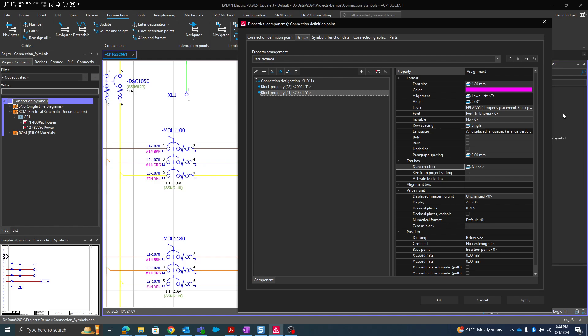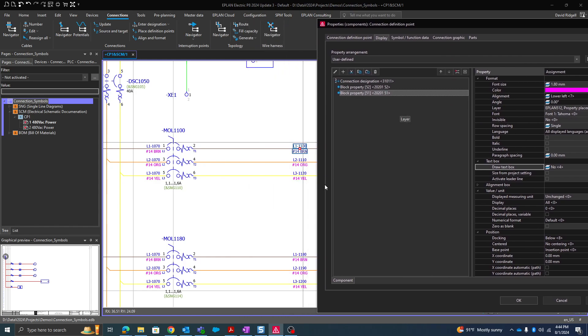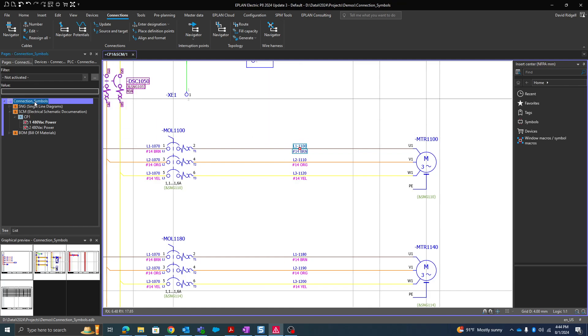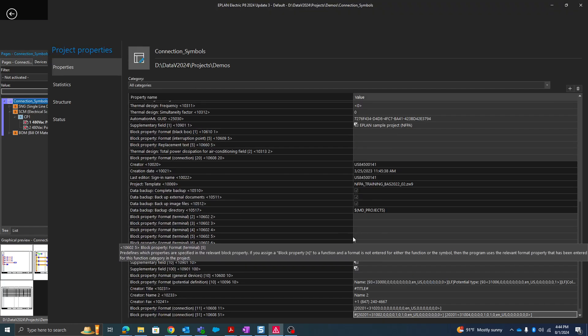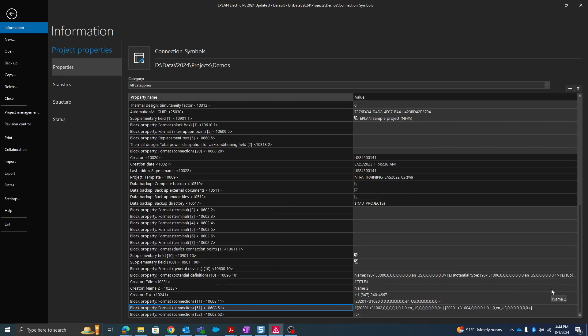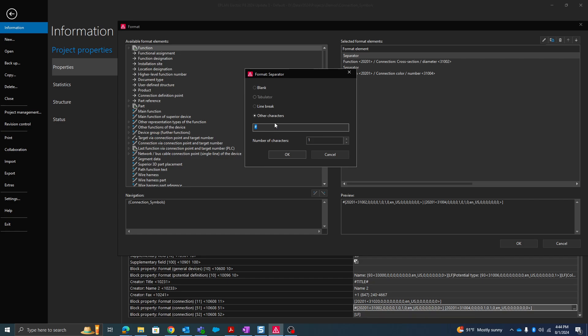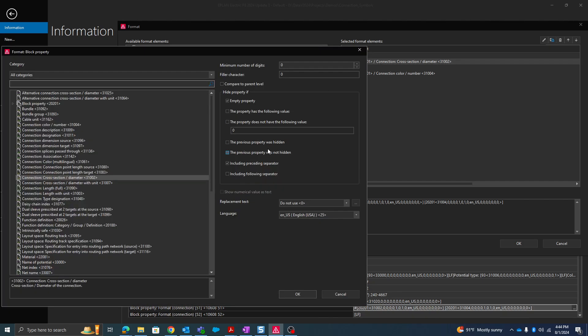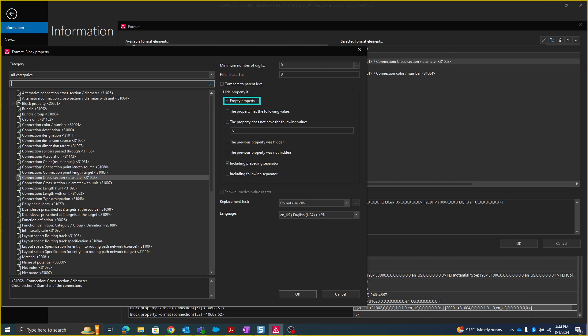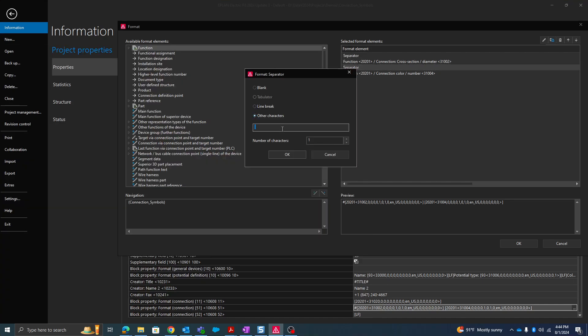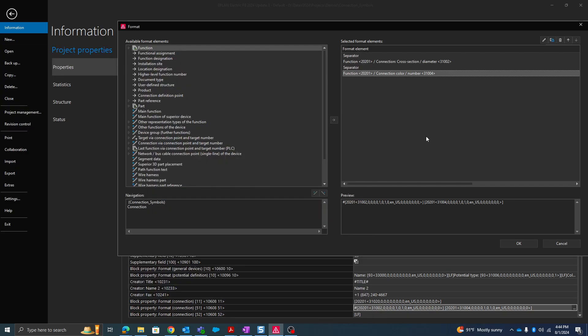If you look here under block property 51, that's what's displaying there. How do I actually see the formatting? This is going to be in the project properties. Block property 51, I'm going to click the three dots. Here I have a separator as the pound sign there. The cross section, and I told it I want to hide if this is empty and also hide the preceding separator. For some reason the cross section was completely empty, I don't want to just see a pound sign. Then we have just a space, and then I have the connection color number. So I basically just concatenated those two properties into one line.